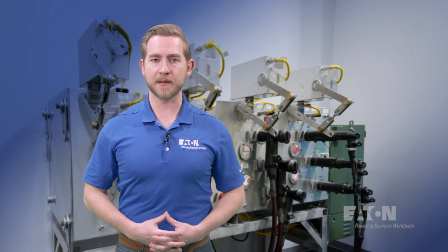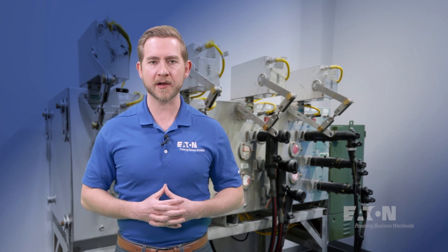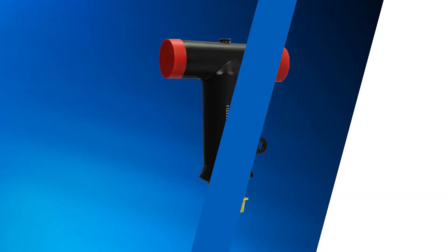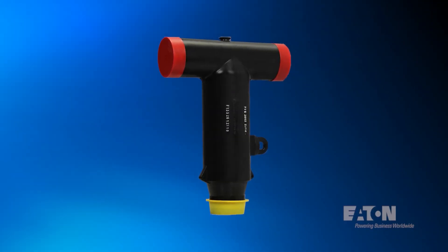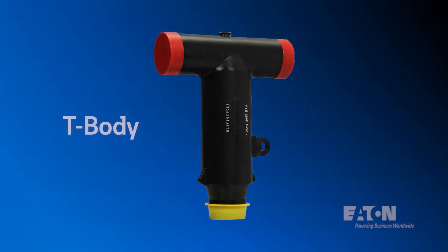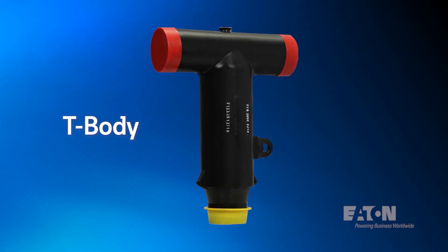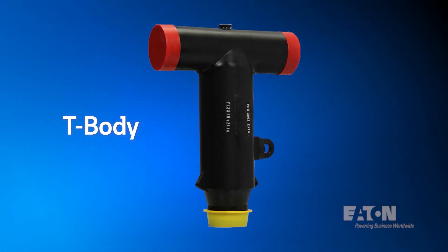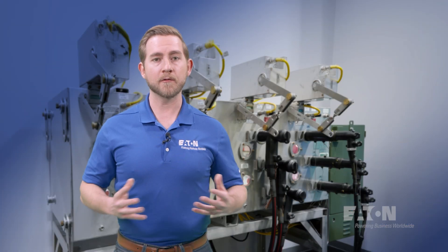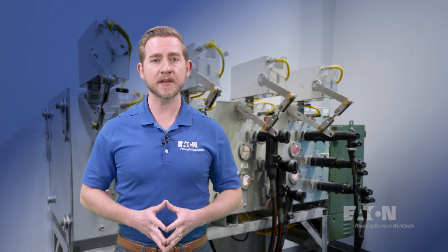Jumping up to 600-amp rated cable accessories requires us to de-energize the equipment before we can make or break a circuit, hence the dead break terminology that we discussed earlier. This time, instead of an elbow-shaped device, the device is shaped like a T, generally denoted in the industry as a T-body. They are bigger than their 200-amp load break counterparts and more robust, and allow the option to connect an additional cable accessory, such as an elbow arrestor, to the other end of the T-body. If we wanted to, we could even interface a 200-amp load break elbow onto one end of the T-body.